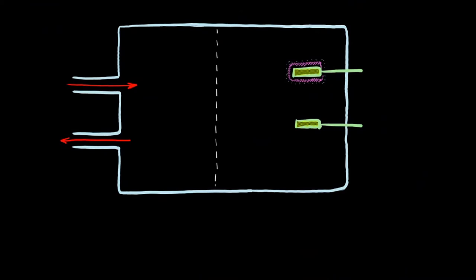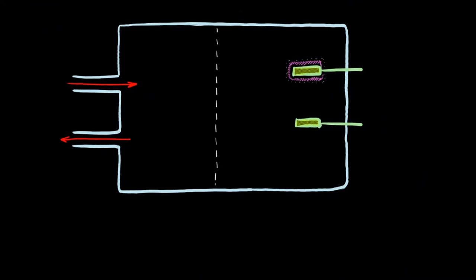Let's now break down the Severinghaus electrode system. This is a simple schematic of the electrode. On the left, we have two connections to the blood sample, or calibrating gas sample. One for flow into the chamber, and another for flow out of the chamber. Inside each chamber, we see the redox reaction happening, keeping the level of carbon dioxide in equilibrium with the level of bicarbonate ion.